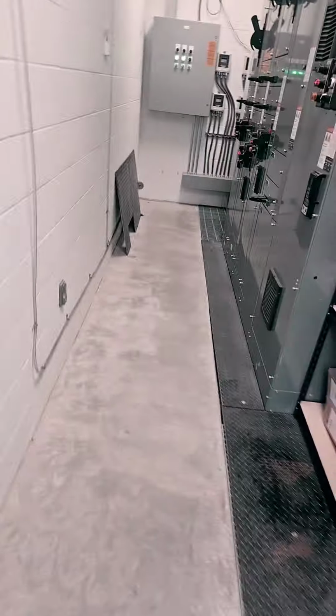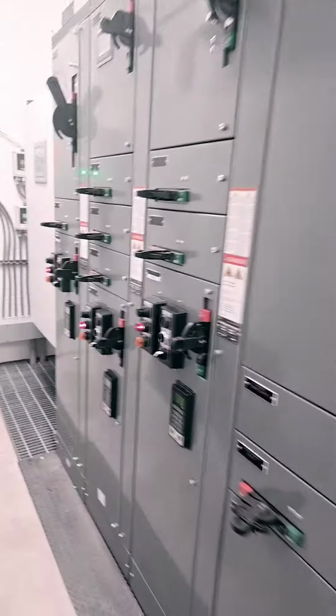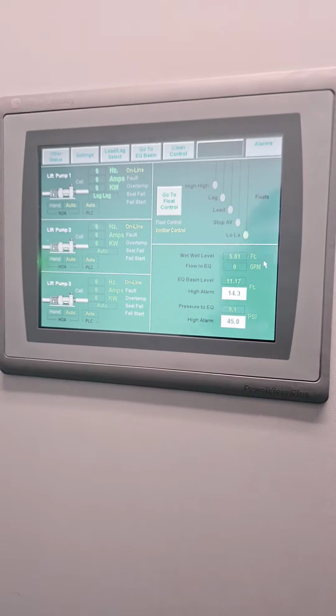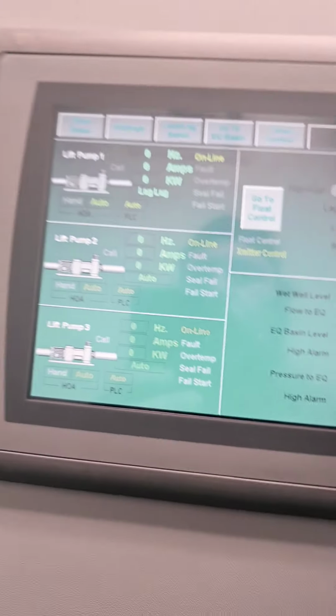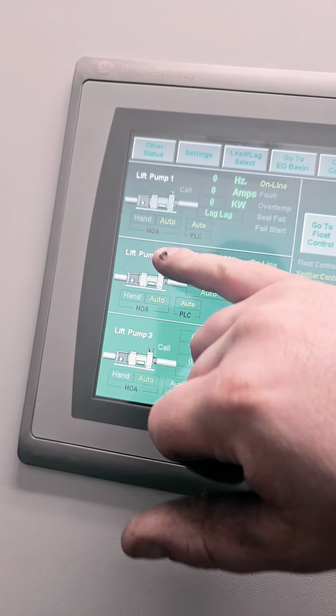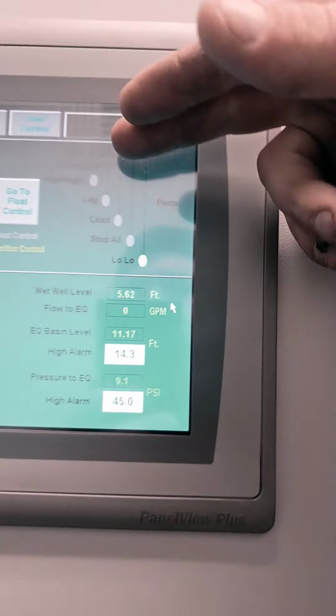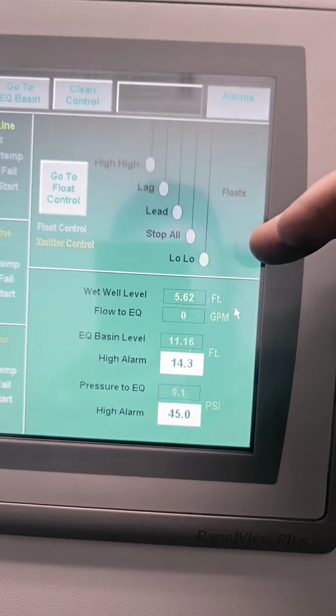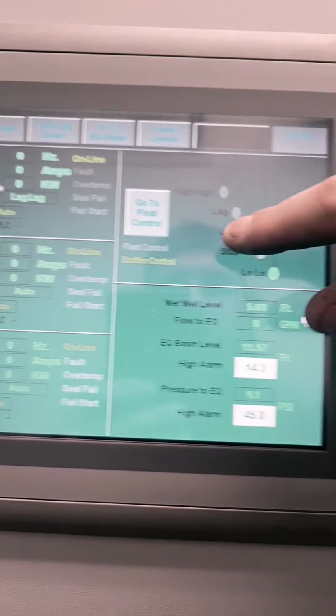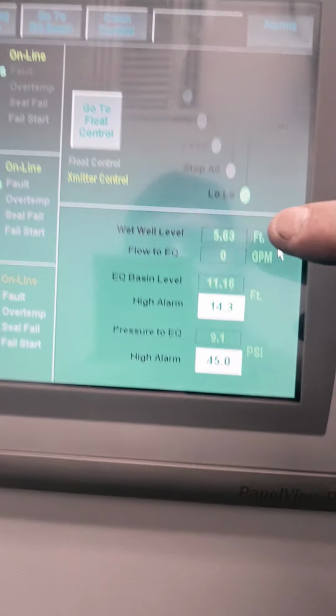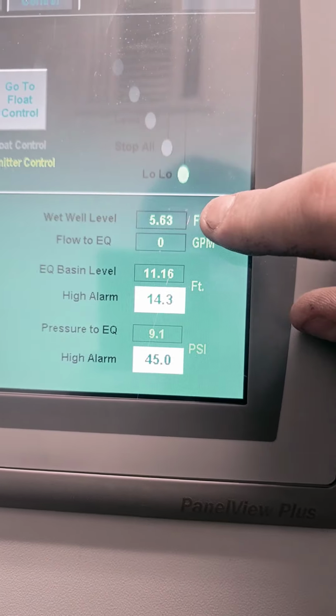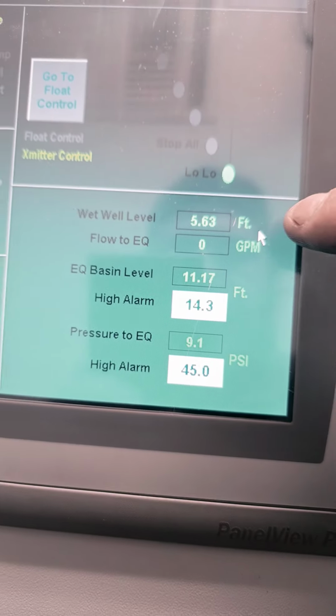Inside here's the electrical room. This has all the power coming in for the pumps. We have a PLC that gives us control over the pumps. These will turn green if the pumps are running. Here are our floats—it'll tell us which floats are tripped and which ones are not. It'll tell us if we're in transducer control, and right here we can see what our transducer is telling us. We're at 5.63 feet, and as that goes up and down, that controls the pumps currently.